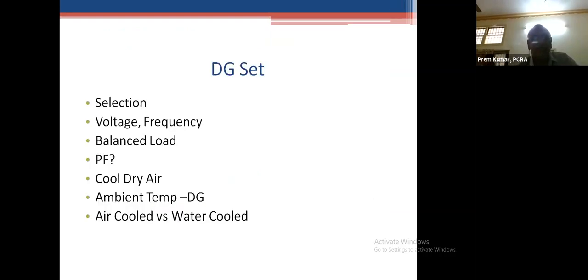So DG set is very similar to that. Selection is very important. Many times they buy a standard DG set and try to size it. Take the support of the DG set supplier for selection. Nowadays, the rental becomes a more viable option because of the improved power quality from the grid. It is better to rent it.